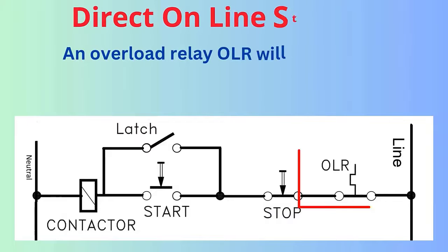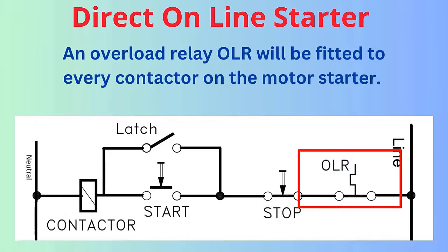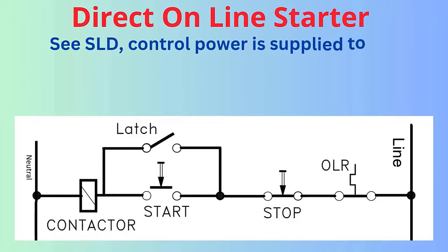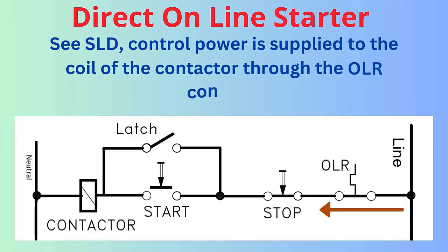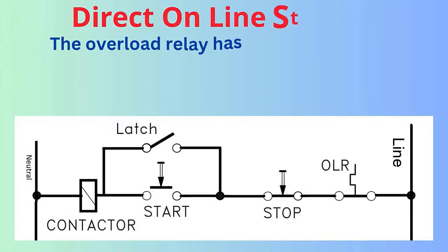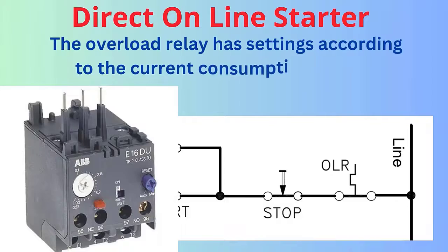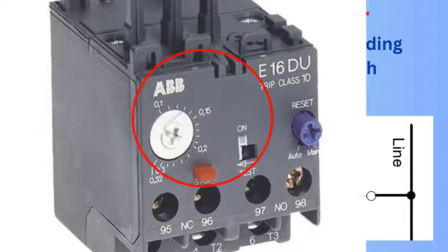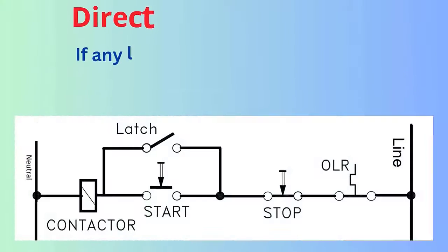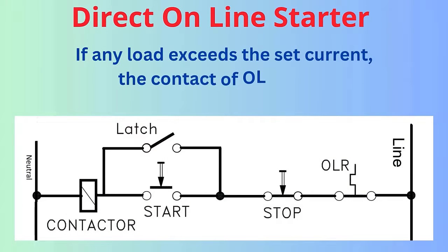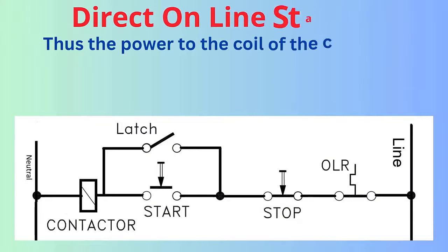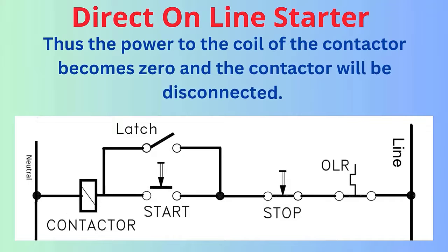An overload relay, OLR, will be fitted to every contactor on the motor starter. See the SLD. Control power is supplied to the coil of the contactor through the OLR contact. The overload relay has settings according to the current consumption of each motor. If any load exceeds the set current, the contact of OLR trips. Thus, the power to the coil of the contactor becomes zero, and the contactor will be disconnected.